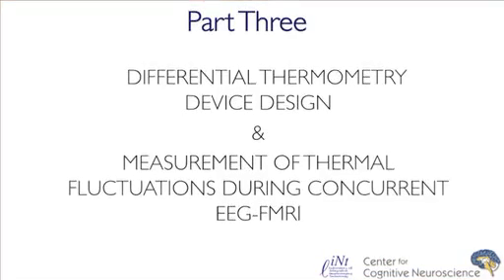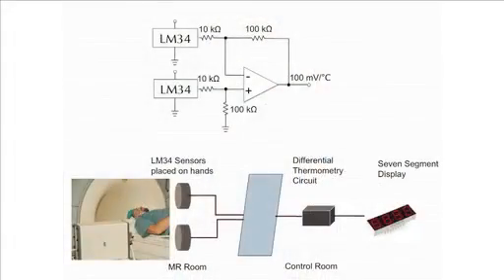We developed a device to collect differential hand temperature measurements during simultaneous EEG fMRI following the hypnotic cold glove suggestion. The device consists of two LM34 temperature sensors connected to an amplifier and a digital display. Two 9-volt batteries supply power to the internal electronics.